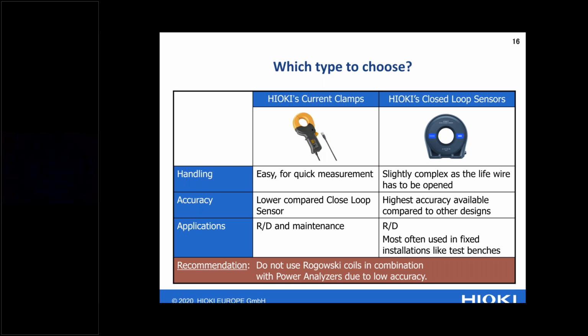One thing we want to definitely highlight is to not use any Rogowski coils, because of the way they're set up—you get more noise. If you already have a high-value measurement system and then use Rogowski coils, that just leads to less accuracy. At the end of the day, you lose what you gained by having a better power analyzer, and that's something we would not recommend doing.